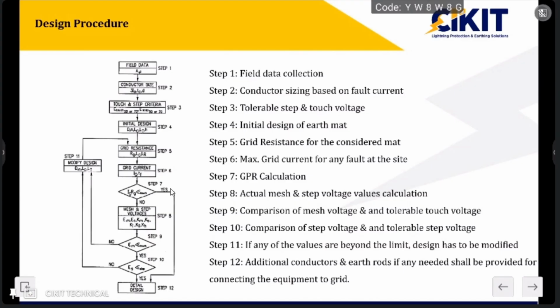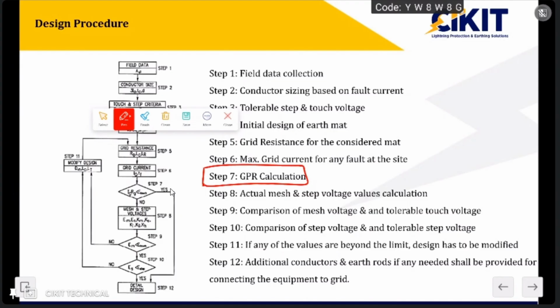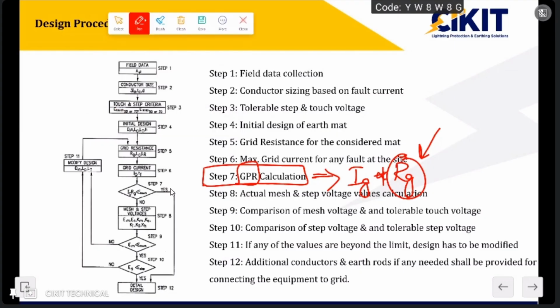So why do we give importance to grid resistance? Only because of the GPR calculations. When explaining GPR, I mentioned that GPR is nothing but the product of Ig into Rg. If the Rg value is maintained low, then because of the lower Rg, the GPR will also be low. If the GPR is low, then the step and touch voltages will be low. That is the reason it is recommended to maintain a lower grid resistance value. They have not mentioned that the grid resistance value should be less than 1 ohm. It should be as low as possible, and for ensuring whether the design is safe or not, they consider only the step and touch voltages, not the grid resistance value as an evaluating parameter. So it is not mandatory to ensure that the value is less than 1 ohm.